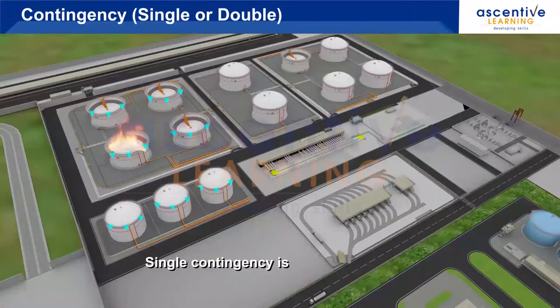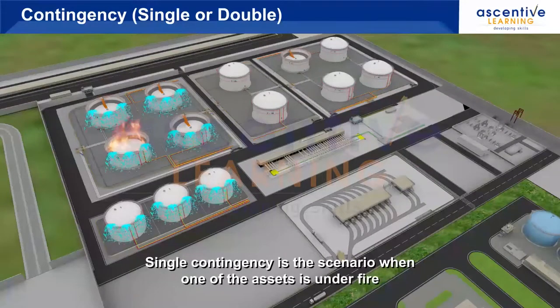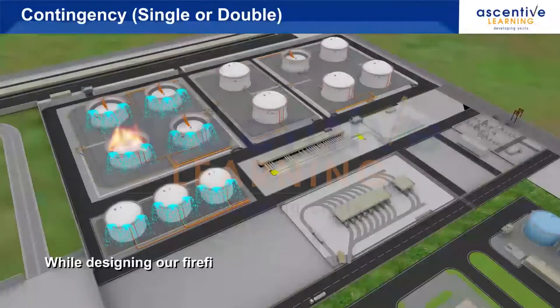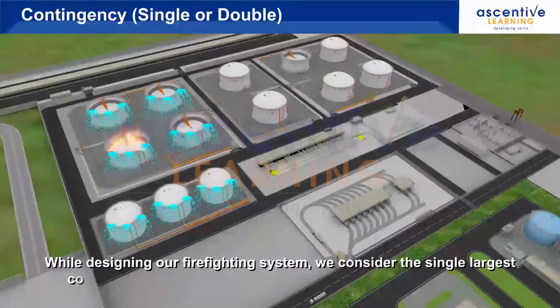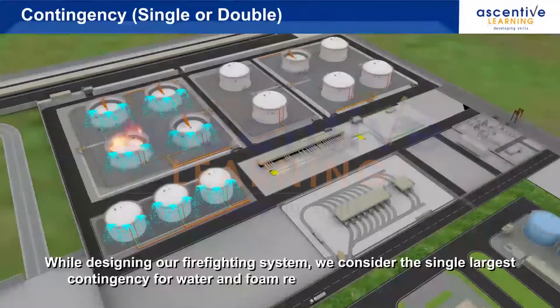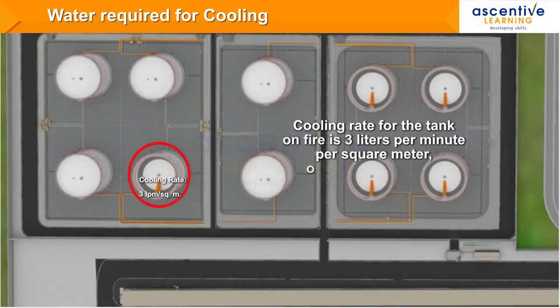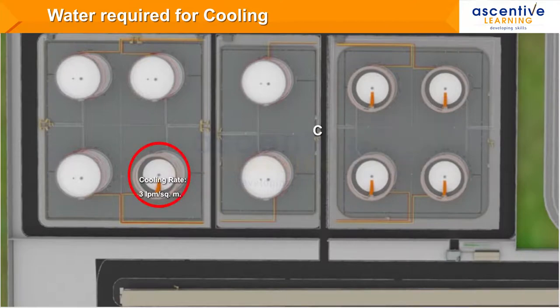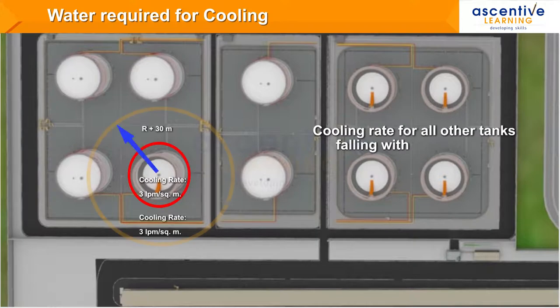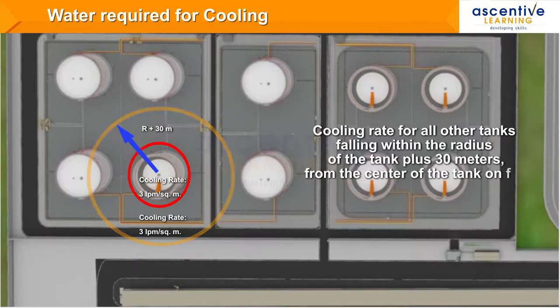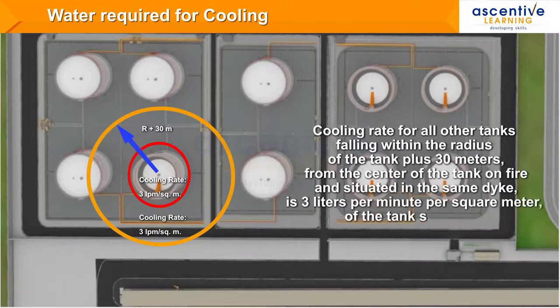Single contingency is a scenario where one of the assets is under fire. While designing our firefighting system, we consider the single largest contingency for water and foam requirement and pumping rates. The cooling rate for the tank on fire is 3 liters per minute per square meter of the tank shell area. The cooling rate for all other tanks falling within the radius of the tank plus 30 meters from the center of the tank on fire, and situated in the same dike, is also 3 liters per minute per square meter of the tank shell area.